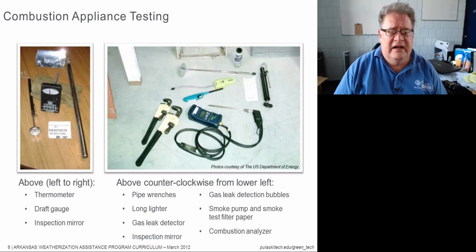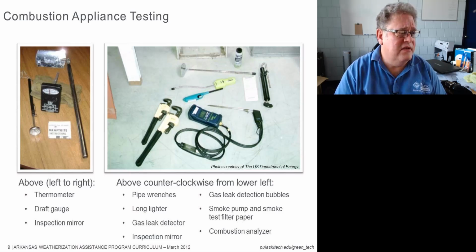So here on the left we have a mechanical, or rather an analog, thermometer. We also have an analog draft gauge, and then an inspection mirror. In this case it's stainless steel. On the right hand picture we have some pipe wrenches, a combustion analyzer, and a gas leak detector, very important for gas fuels. We have another inspection mirror, some leak detection bubbles, and you may not be able to see those real well, but there they are.